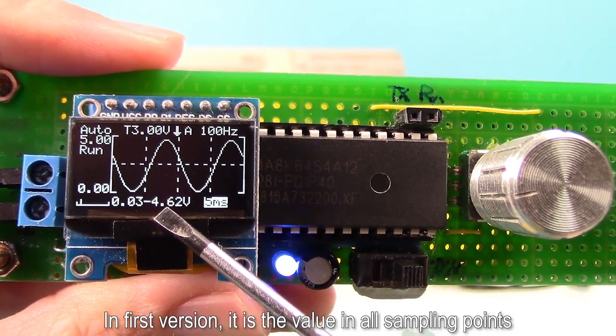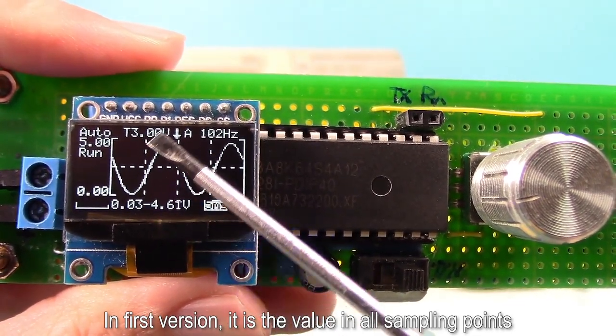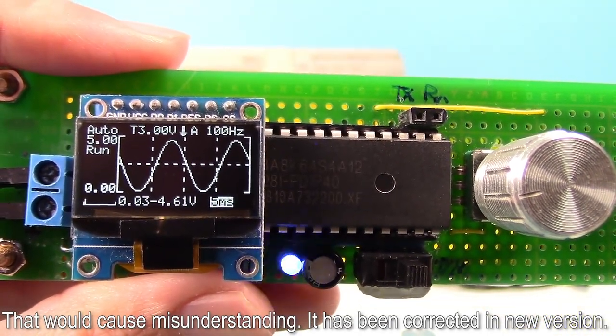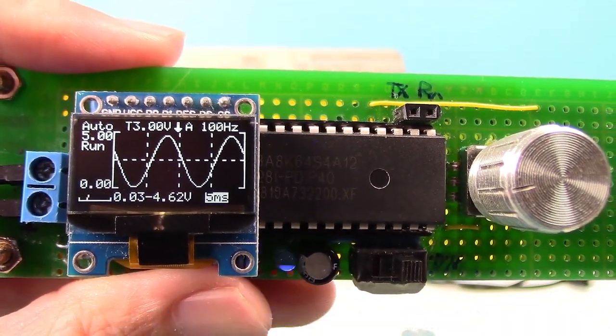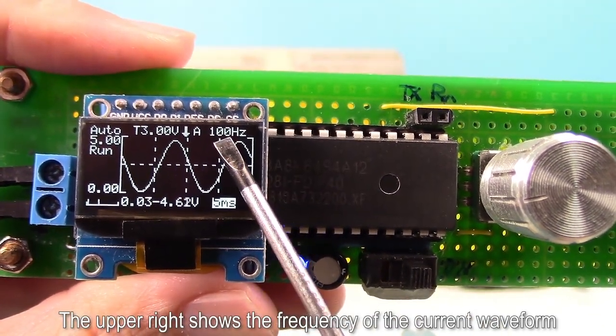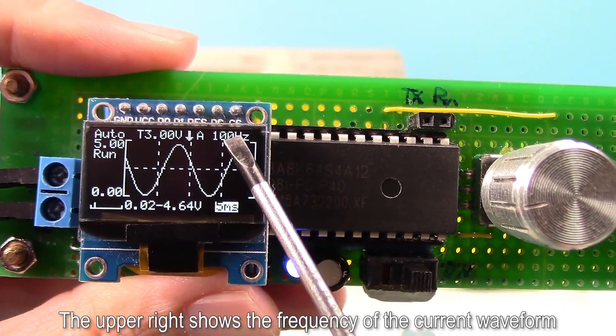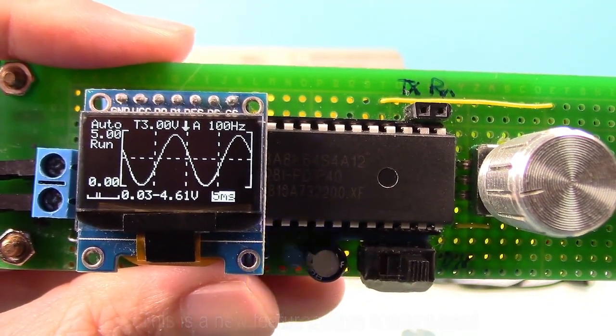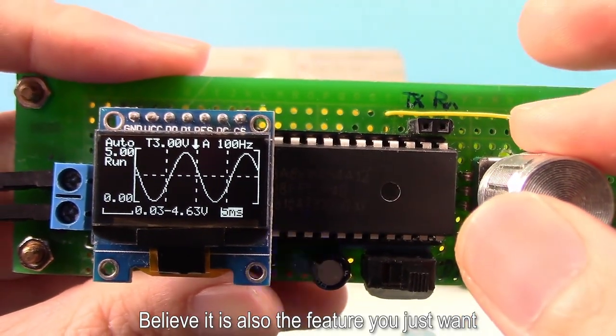In first version, it was a value in all sampling points. That would cause misunderstanding. It has been corrected in new version. Beside it is seconds per division. The upper right shows the frequency of current waveform. This is a new feature which is very useful. Believe it is also the feature you just want.